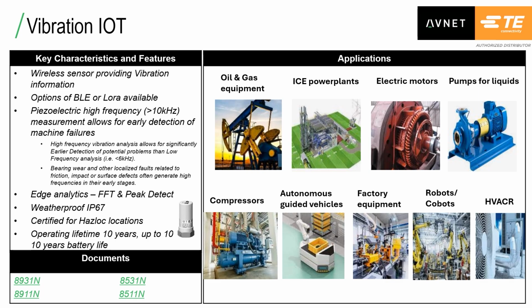High-frequency vibration analysis allows for significantly earlier detection of potential problems, as opposed to low-frequency analysis. Also, bearing wear and other localized faults related to friction, impact, or surface defects often generate high frequencies in their early stages, and these can be captured. It also provides full edge analytics, including fast Fourier transforms and peak detect. It has an operating lifetime of at least 10 years with up to 10 years of battery life. Some of the key applications for TE's wireless vibration sensors include oil and gas equipment, internal combustion engine power plants, motors, pumps, compressors, and autonomous guided vehicles, or AGVs.